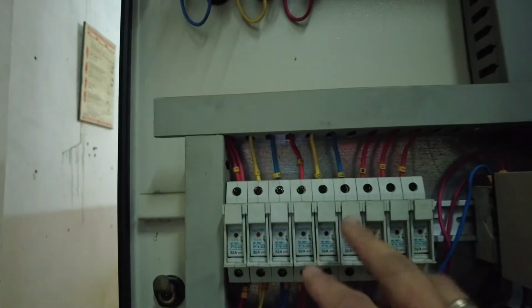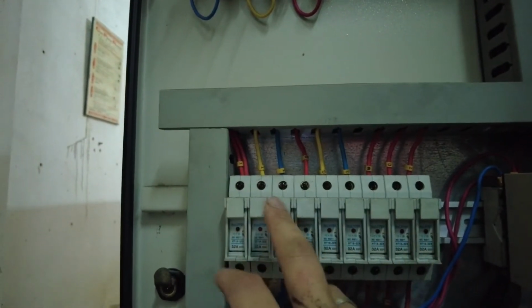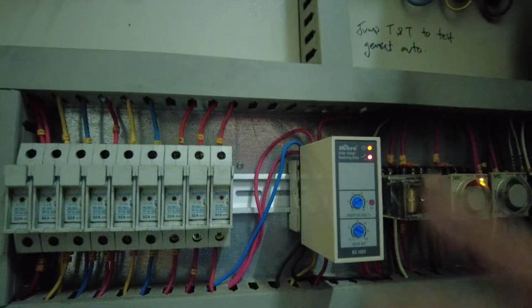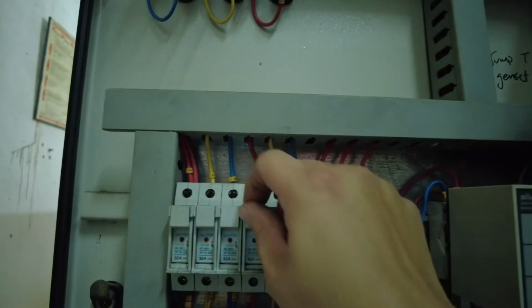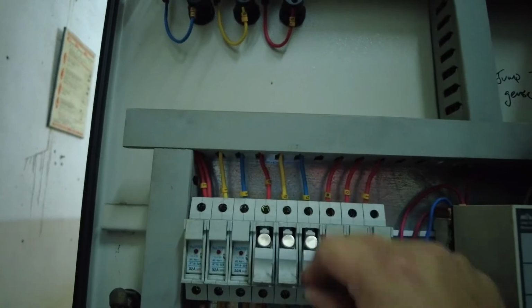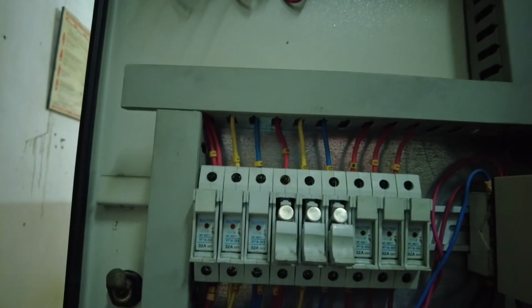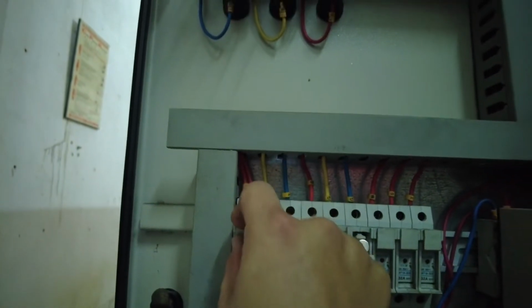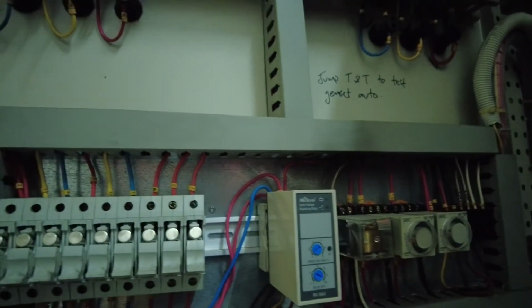Alright, here we are at the LV room. Okay, so here we have the genset fuse and the main supply fuse going to the UVR relay. So now we're going to trigger this thing. Okay, first of all, we take out the genset fuse because we don't want the ATS to operate and change over. Alright, and then we take out this fuse to allow the UVR to trigger. Oh, genset already running.